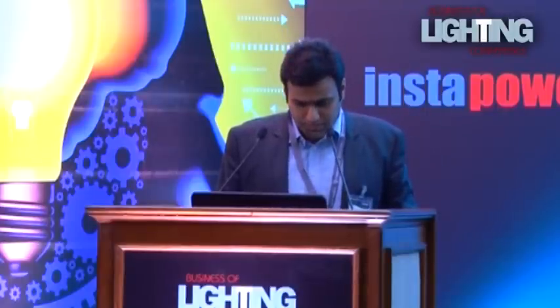My LPD goes up, however my cooling load comes down because the direct heat coming onto my workstations within my ambient air is minimal. Moving forward, I talk about LEDs. LEDs have reduced my LPD to 5.86 watts per square feet.